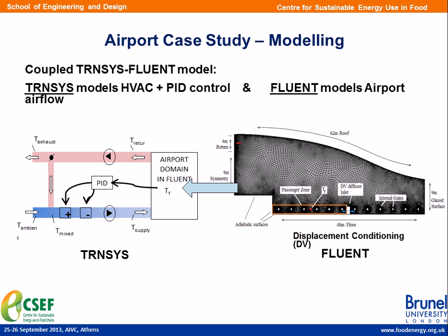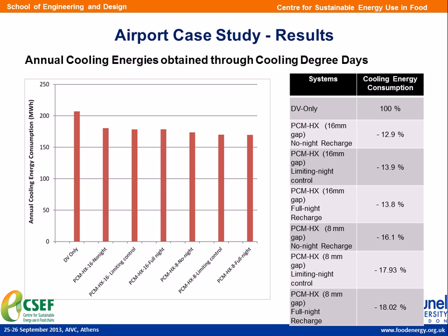The study was done with TRNSYS and Fluent. TRNSYS modeled the HVAC system and the PID control system, and Fluent models the airport airflow. These are coupled together, and the model has been calibrated using laboratory testing. The developed model has looked at different parameters, and it indicated that 18% energy savings can be achieved by an 8 millimeter gap PCM heat exchanger with a full night charge.